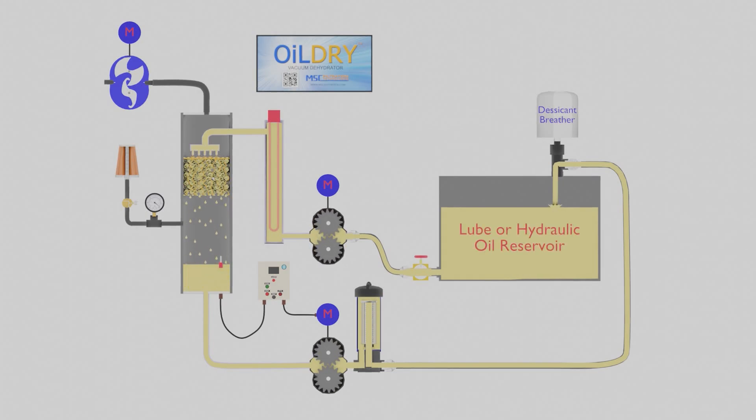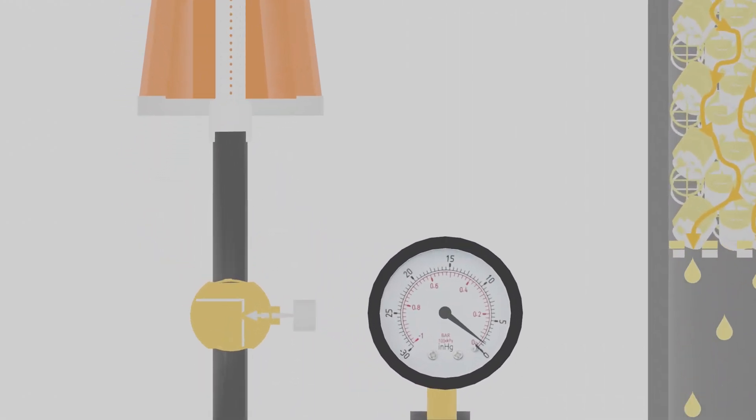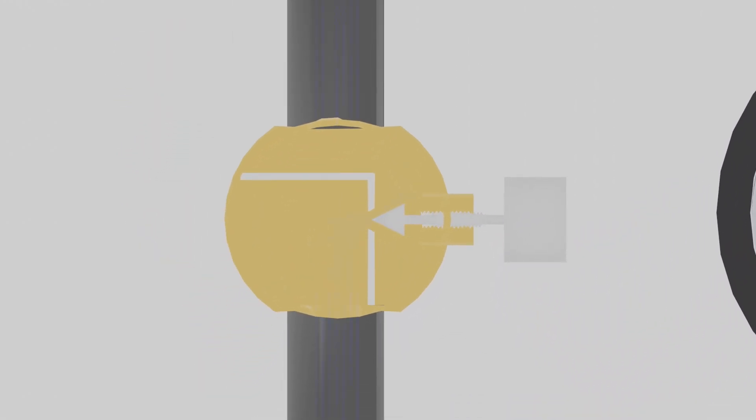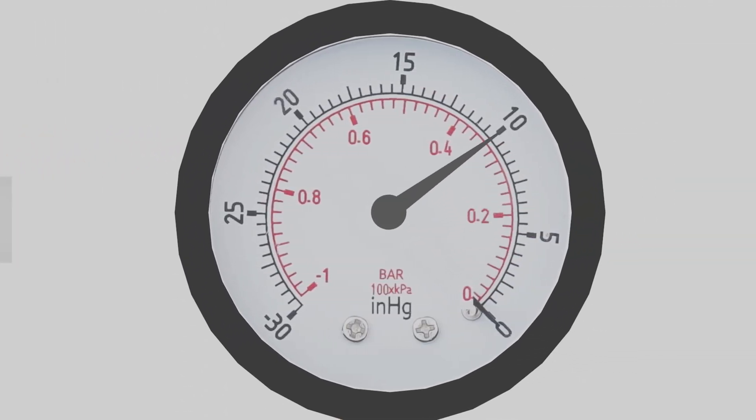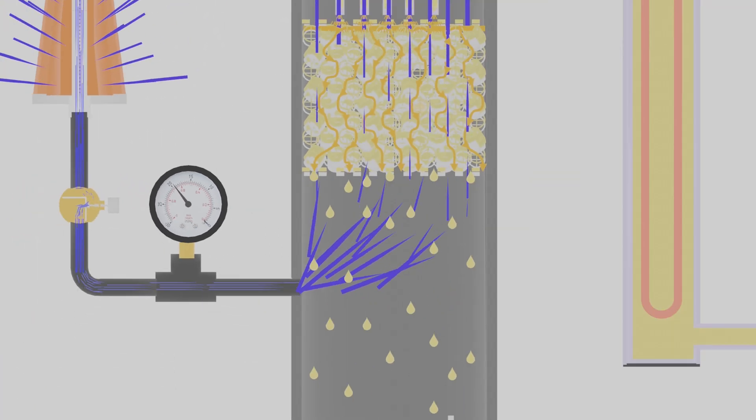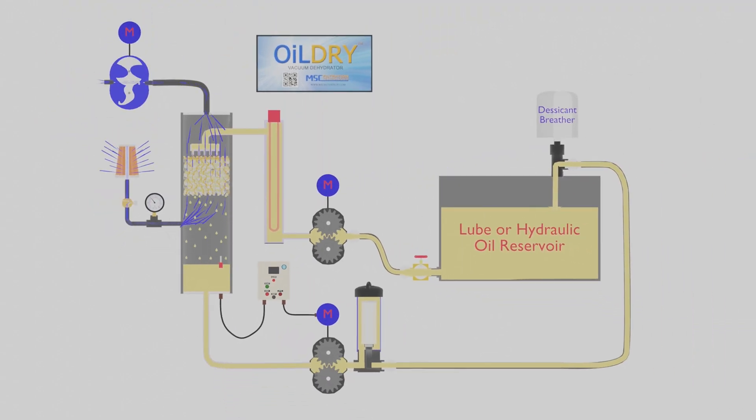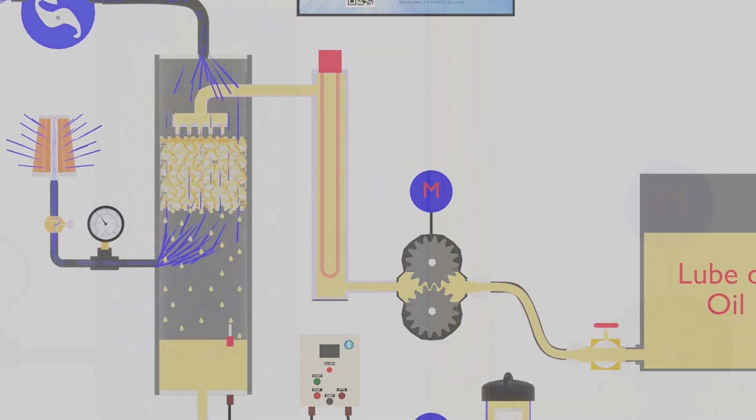Next, a low-maintenance, high-durable, claw-style vacuum pump pulls filtered atmospheric sweep air into the vacuum tower, whose flow once restricted creates a vacuum of up to 18 to 20 inches in the tower. Sweep air under vacuum then passes across the porous packed bed in a counter-current flow, allowing the process of water evaporation and removal to begin.